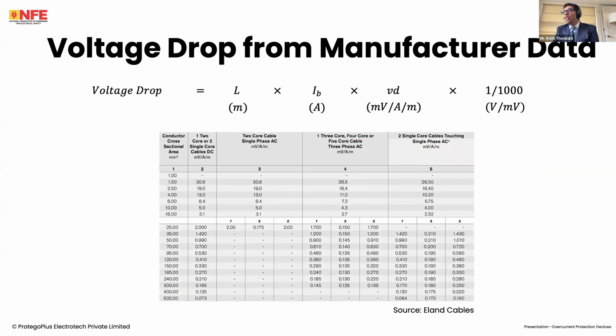There are two ways. I'll show you the easier and more conventional way, which is calculation of voltage drop from manufacturer data. A manufacturer will say, for a certain cross-sectional area of cable, whether it is a two-core, three-core, four-core or five-core cable, and whether it is touching or spaced out, there is a certain voltage drop. But as we know, voltage drop is not only resistive, it is also reactive. So there's inductance and capacitance coming into play here. They provide a value of volt drop in millivolts per amp per meter. You multiply this value by the design current and the length, and because you are in millivolts, you convert to volts, and we get a value. I'll show you an example.